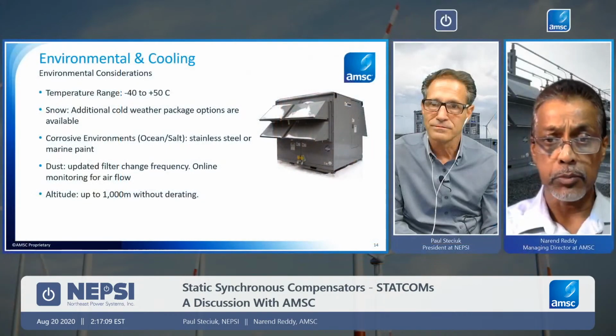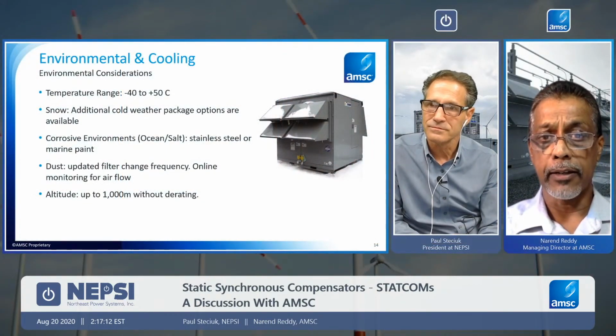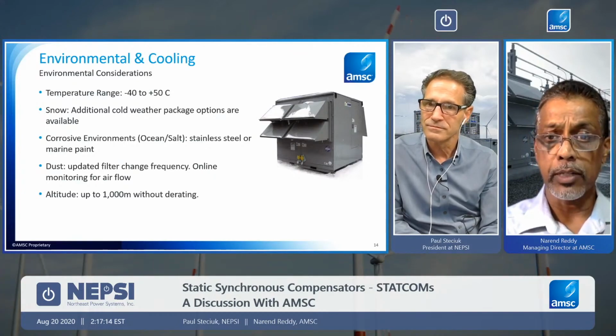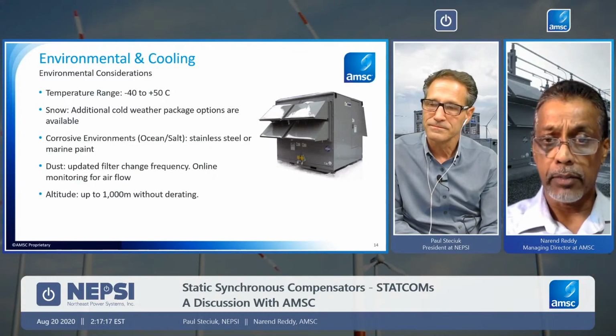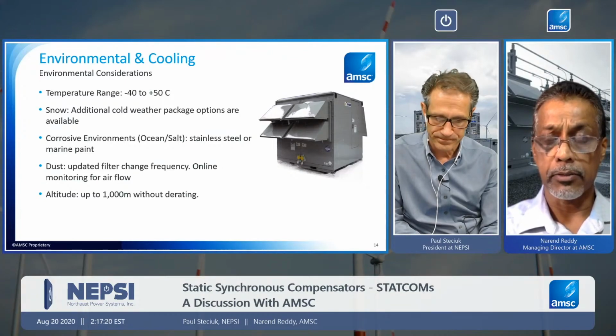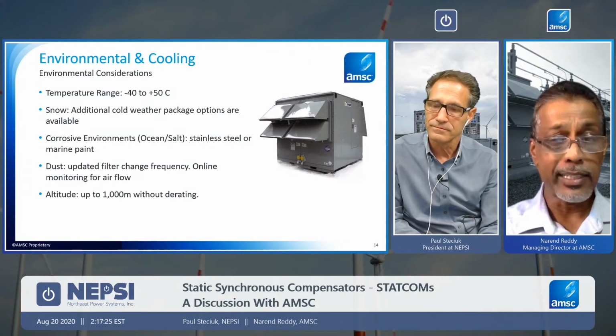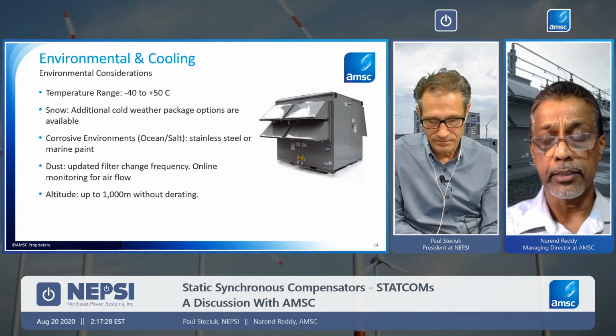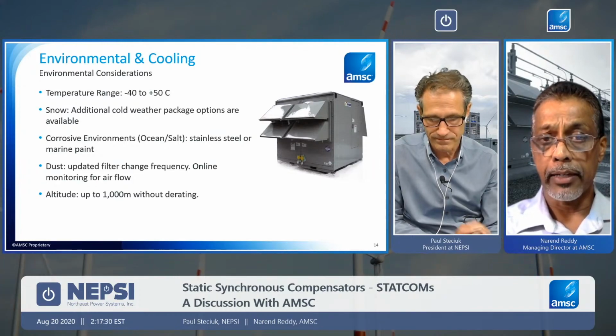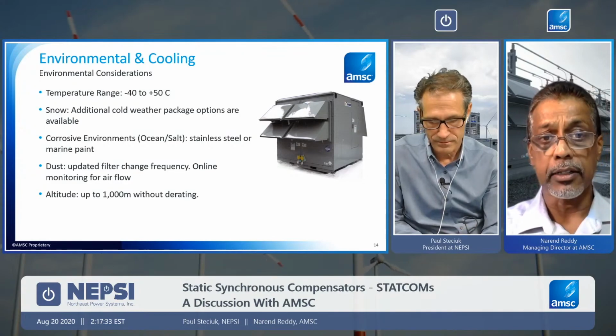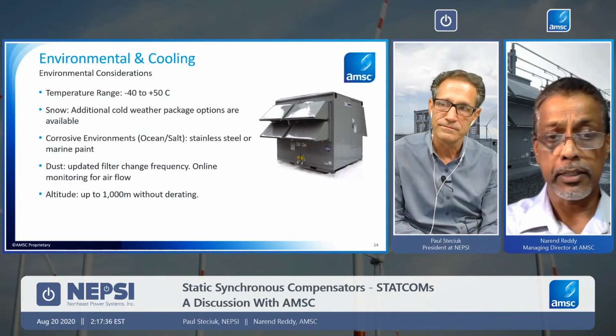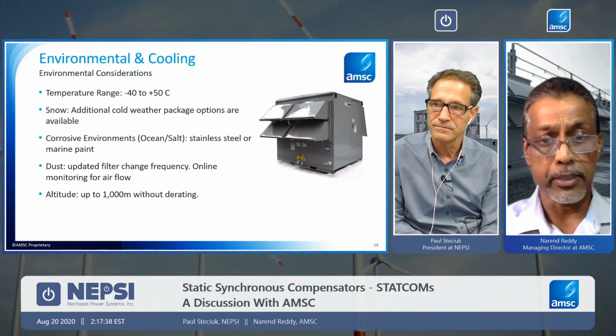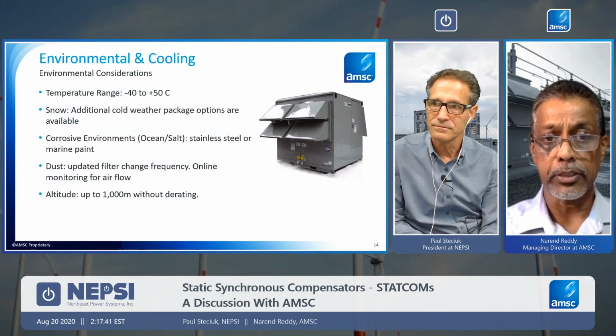As you can see in this picture, there's a cold weather package. If the site is going to have some snow, we can do that. If it's going close to an ocean environment, we have stainless steel or marine paint options for the enclosure, and also for the transformers. One thing to note is that this Statcom is an air-cooled device, so it has air filters in there, and those filters, as I'll talk about a little later, do require some replacement every now and then, but it's a very, very simple replacement procedure.